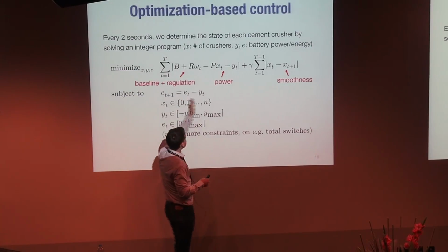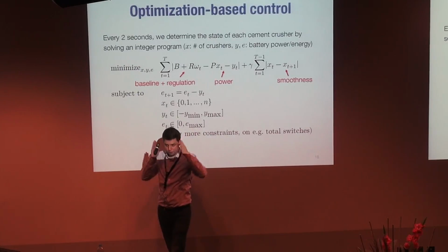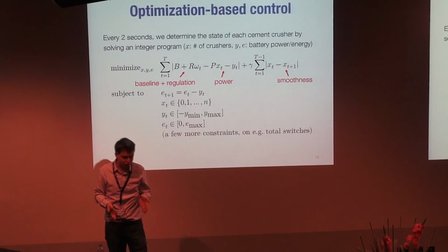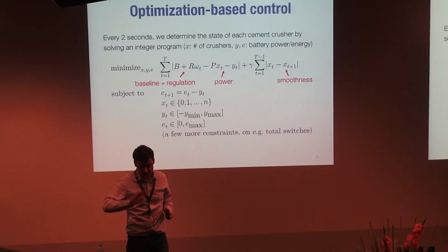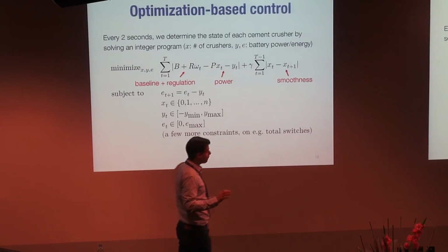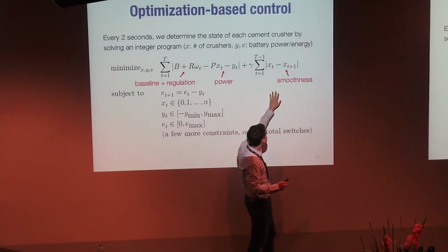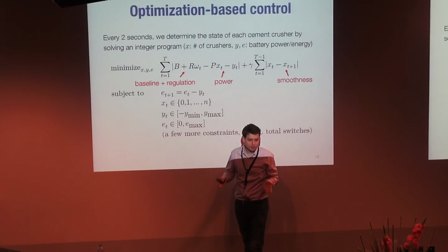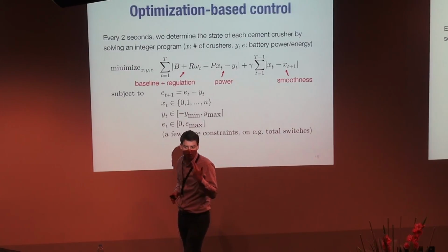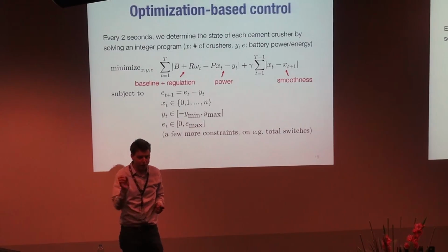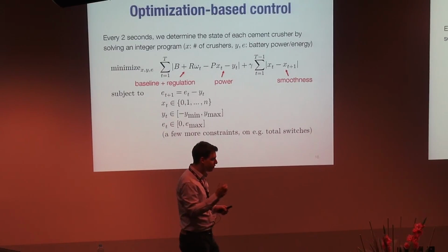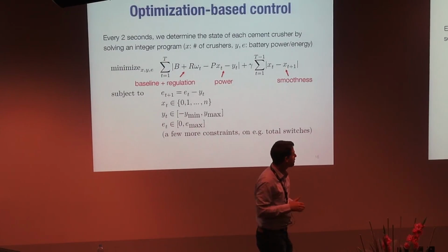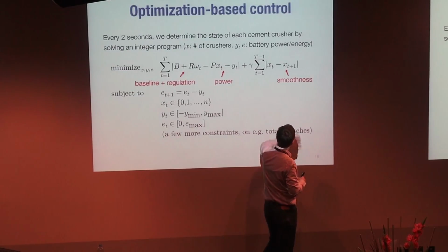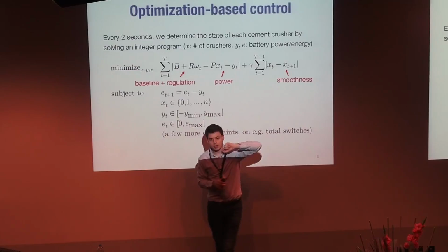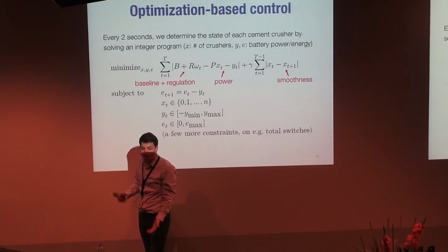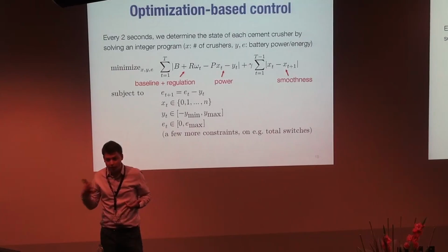We minimize an L1 norm here, meaning we typically want those to be equal. You can have them be equal always if you want, but we allow a little slack because sometimes you'd rather balance another control objective: the smoothness of turning these crushers on and off. You don't want them switching every couple seconds, three on, then one, then two. So you want to enforce a smoothness penalty, and by varying gamma you can trade off between fitting the regulation and how smooth the control signal is.